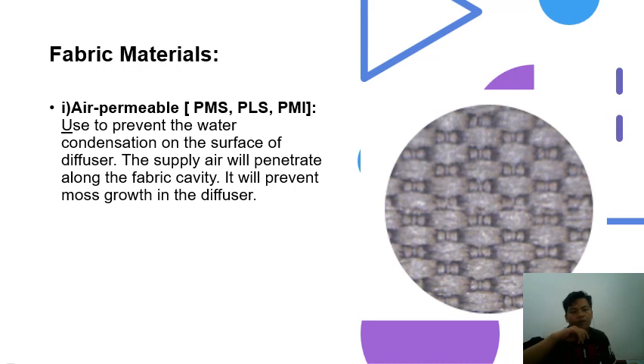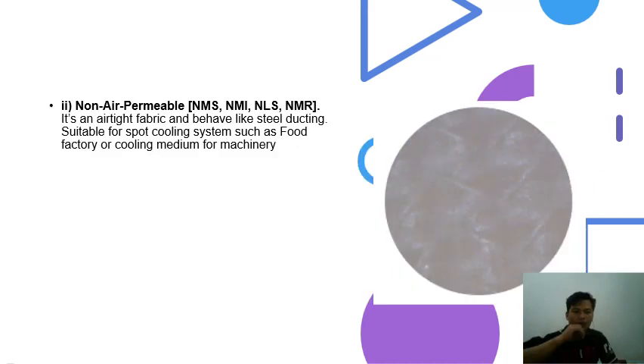Usually, we have two common fabric materials, which are air permeable and non-air permeable. The first one is air permeable, used to prevent water condensation on the surface of the diffuser, and the supply air will penetrate along the fabric cavity. It will prevent mold growth in the diffuser. The second one is non-air permeable. It is airtight fabric that behaves like a steel ducting. It's suitable for spot cooling systems such as food factories or cooling medium for machinery.